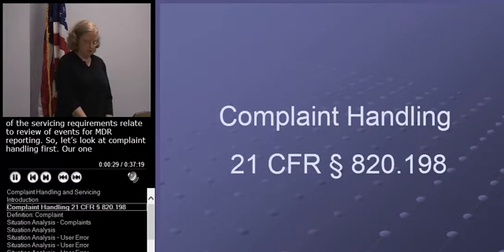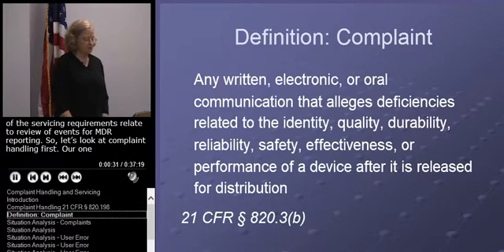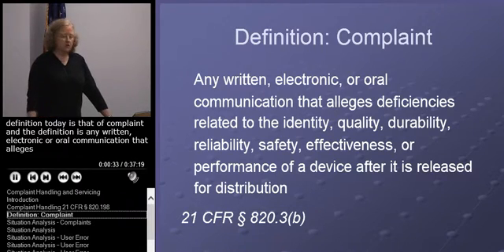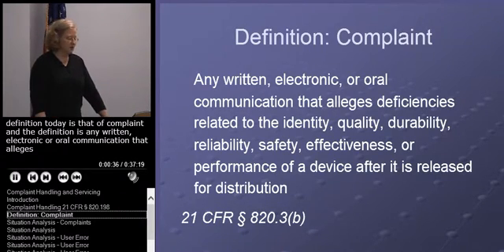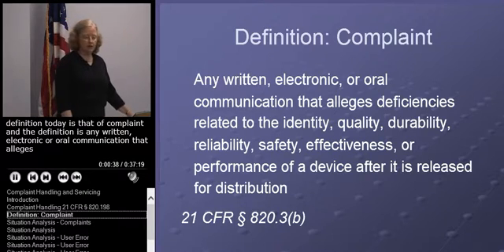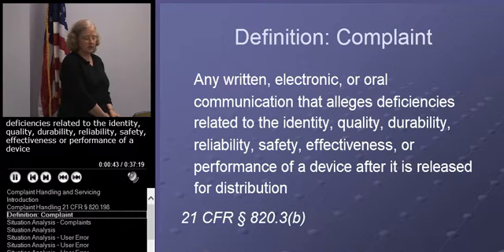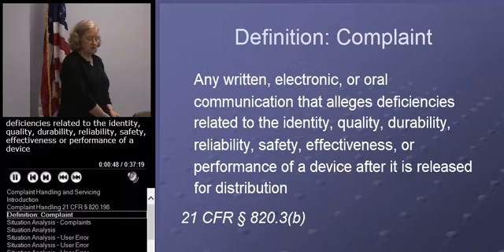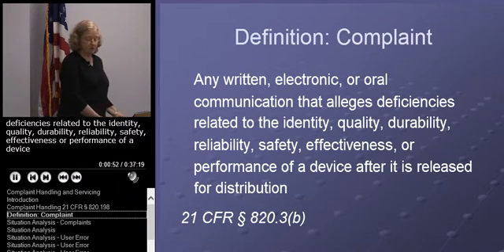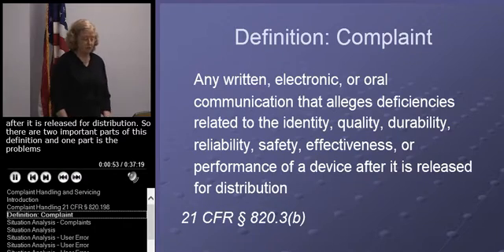Let's look at complaint handling first. Our one definition today is that of complaint, and the definition is any written, electronic, or oral communication that alleges deficiencies related to the identity, quality, durability, reliability, safety, effectiveness, or performance of a device after it is released for distribution.